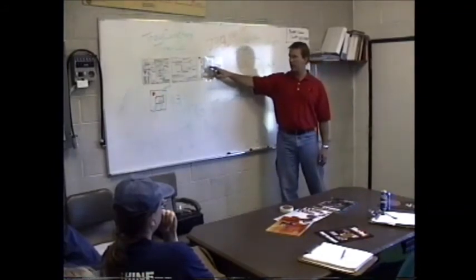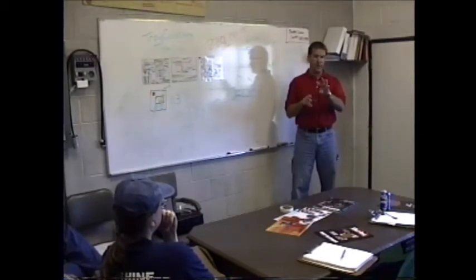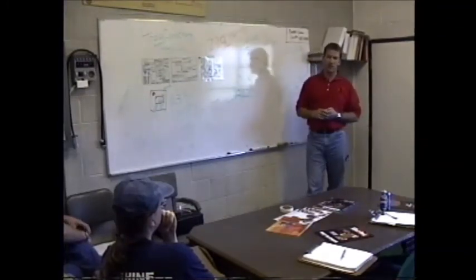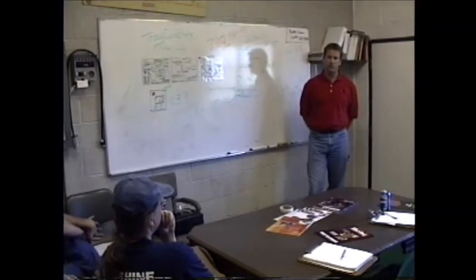We used to put that valve and this manual pressure control adjustment valve on the pump panel. You'd have a manual pressure adjust and a manual automatic valve on the pump panel that you could tinker with, and they were always getting tinkered with. I was always getting called: our compressor system's blowing the poppet valve, or our compressor system won't build any air pressure. Almost 99% of the time, somebody was tinkering with those settings.